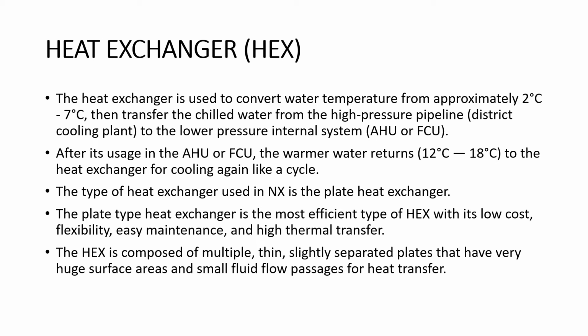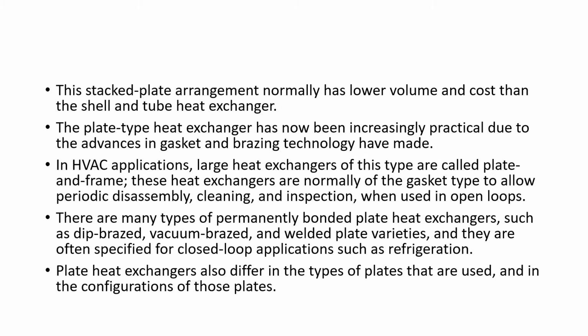The plate type heat exchanger is the most efficient type of HEX with its low cost, flexibility, easy maintenance, and high thermal transfer. The HEX is composed of multiple thin, slightly separated plates that have very huge surface areas and small fluid flow passages for heat transfer. This type of plate arrangement normally has lower volume and cost than the shell and tube heat exchanger. The plate type heat exchanger has now become increasingly practical due to advances in gasket and brazing technology.